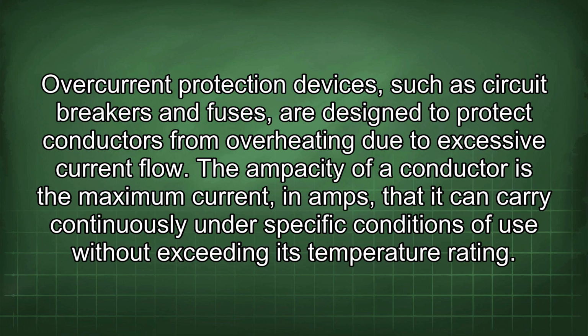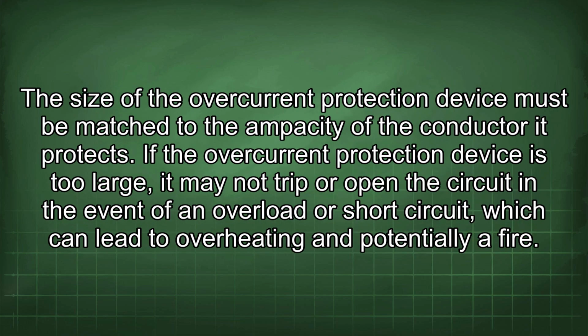flow. The ampacity of a conductor is the maximum current in amps that it can carry continuously under specific conditions of use without exceeding its temperature rating. The size of the overcurrent protection device must be matched to the ampacity of the conductor it protects. If the overcurrent protection device is too large, it may not trip or open the circuit in the event of an overload or short circuit, which can lead to overheating and potentially a fire.